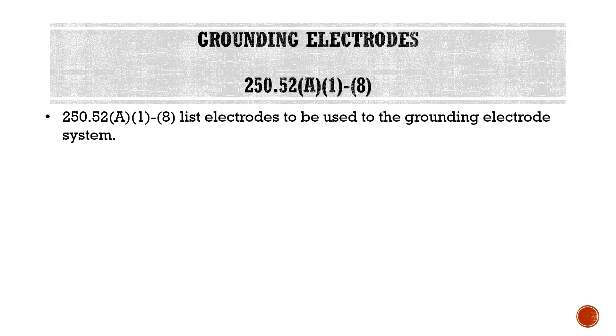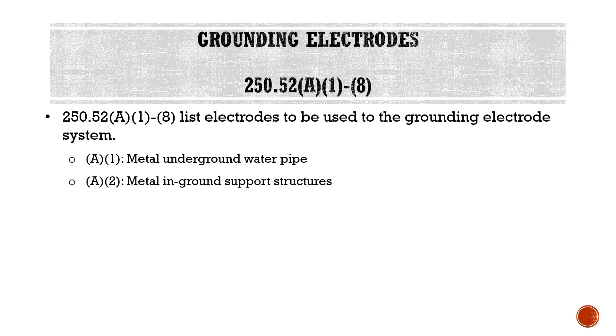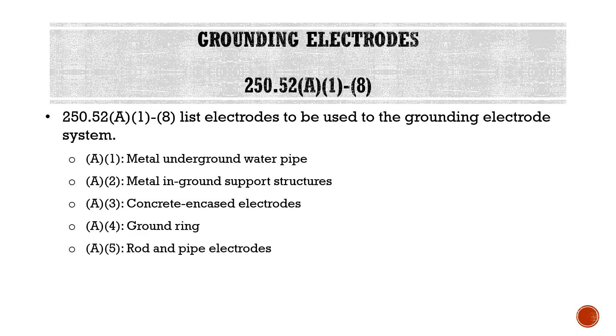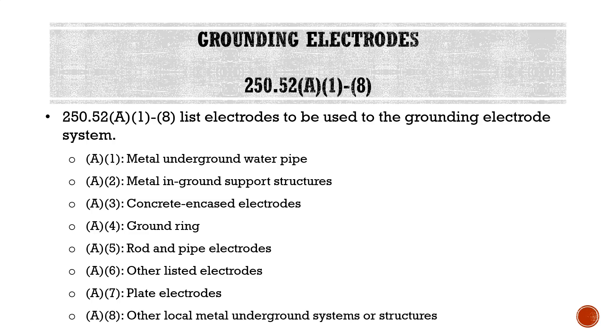Looking at 250.52 A1 through A8 for our grounding electrodes: A1 is metal underground water pipe. A2 is metal in-ground support structures. A3, concrete encased electrodes. A4, a ground ring. A5, rod and pipe electrodes. A6, other listed electrodes. A7, plate electrodes. And A8, other local metal underground systems or structures.